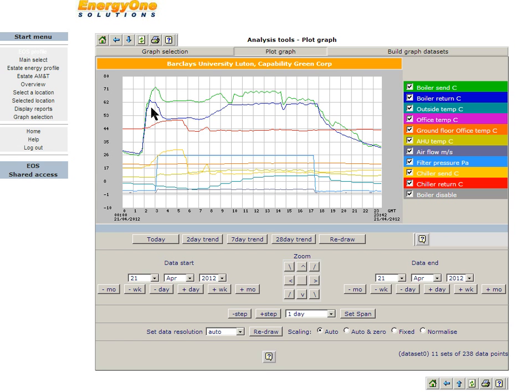The chiller return reacted to a small return temperature increase, and this resulted in the air handling unit coming on at 4 a.m. So the heating and cooling were both running at the same time, yet the space temperatures remained stable. All this activity and consumption taking place many hours before people arrived at the building. When they did arrive, they found the temperature comfortable, but had no idea how much energy was being consumed to no effect on the space temperatures, a complete waste of resources.